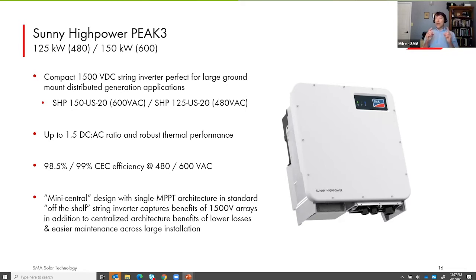And so they are designed with a single tracking channel. Again, the assumption is that we'll have the ability to have many, many strings of the same length, all the same orientation, feed each inverter. But these, while they seem large for a string inverter power class, they're very small if you compare them to SMA central inverters. These are much smaller power conversion units, easier to manage. They are also standard off-the-shelf devices. There's no customization, which is in complete contrast to our central inverters.